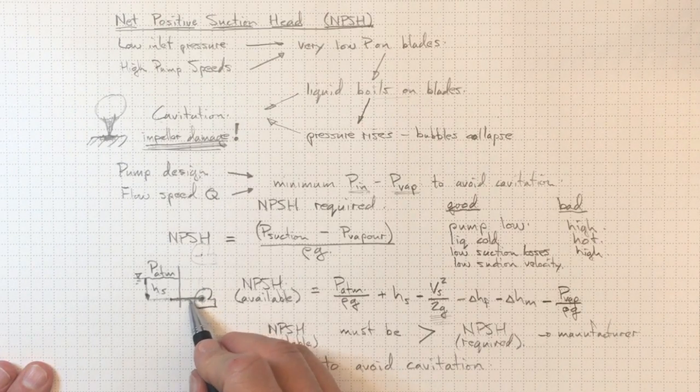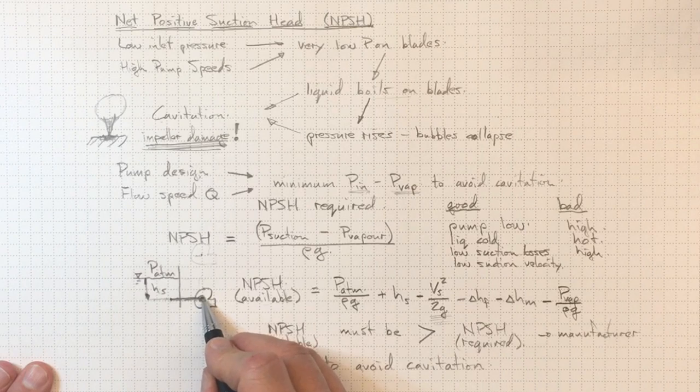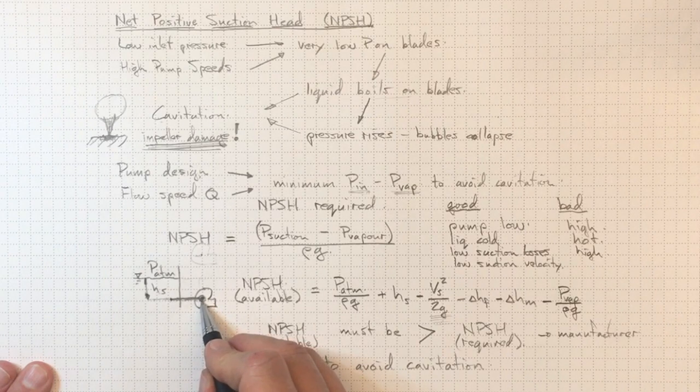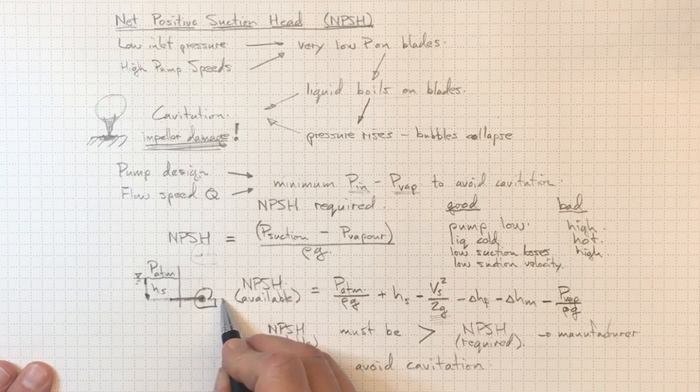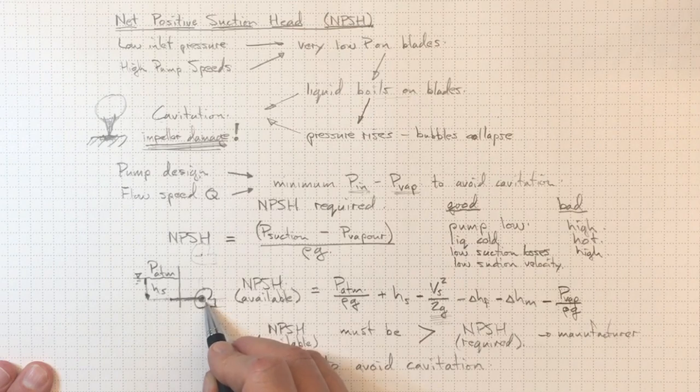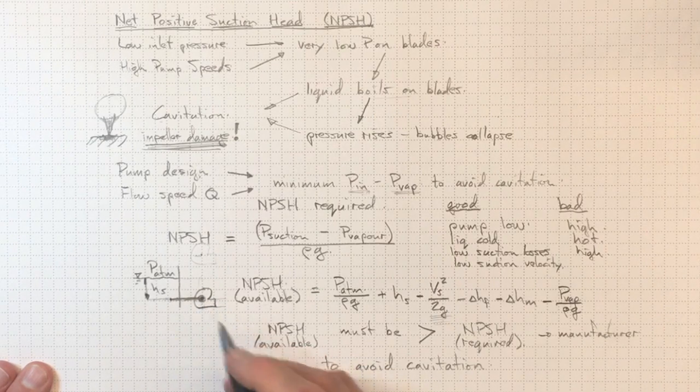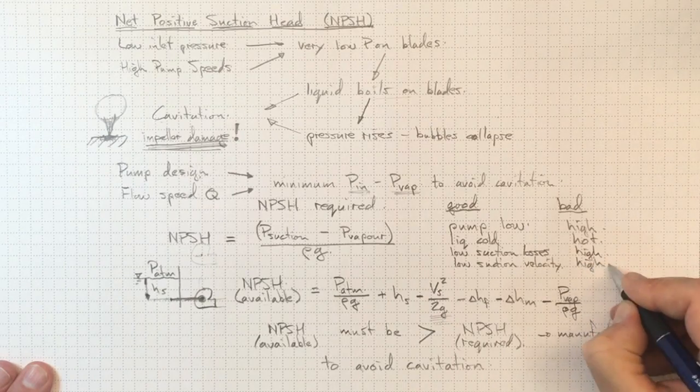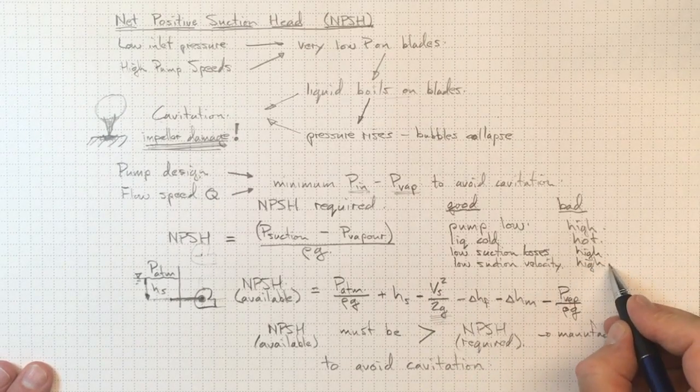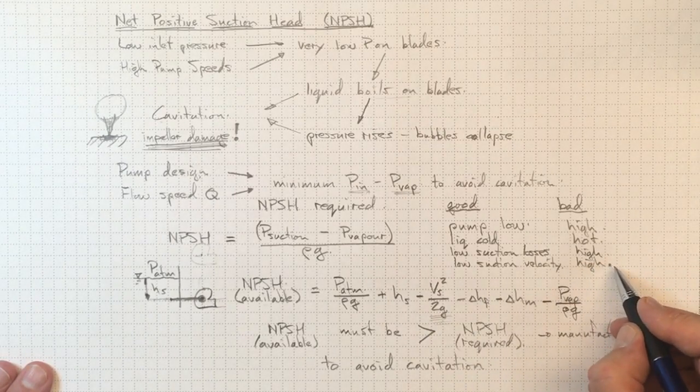So that's why you'll often see that the inlet nozzle on a pump, the inlet pipe connection, is actually larger than the discharge pipe connection. That's to allow for the NPSH and to keep the NPSH requirement low. Of course, the opposite is bad. If we have a high suction velocity, then we may have NPSH problems.